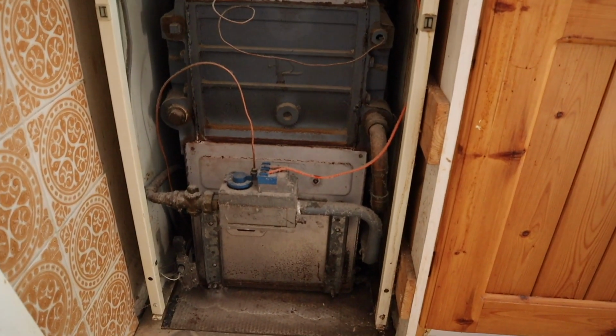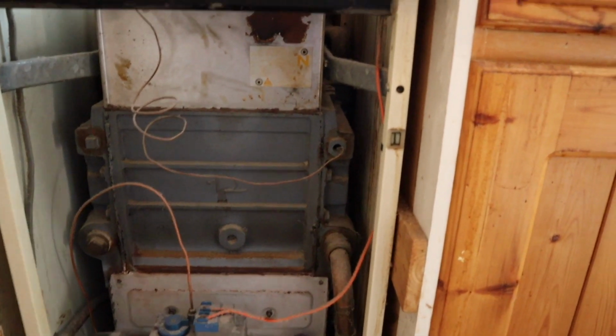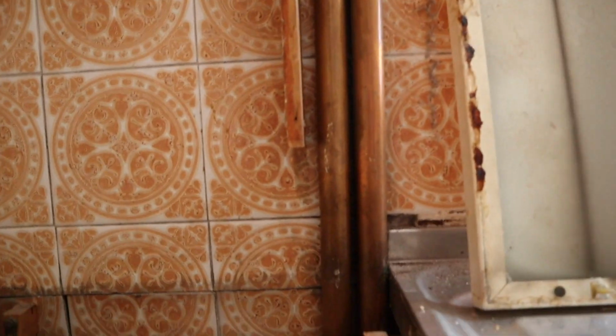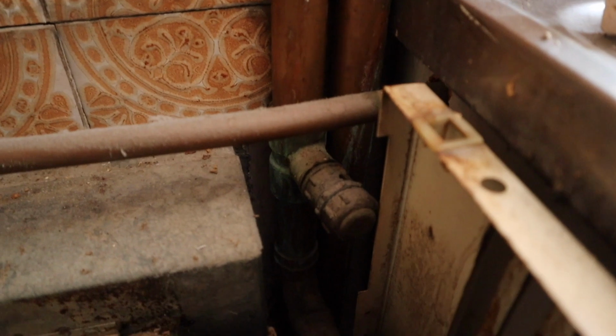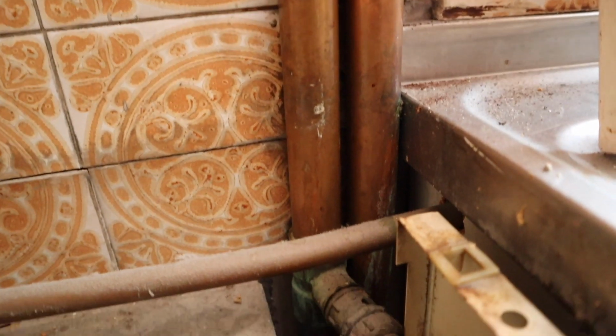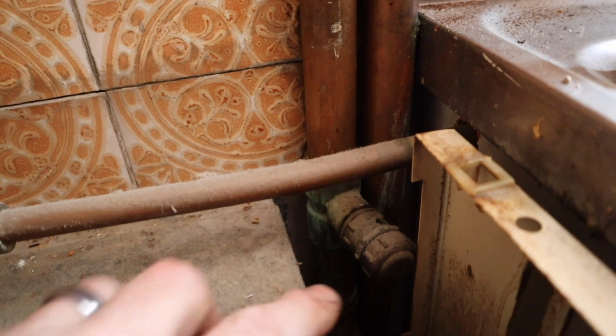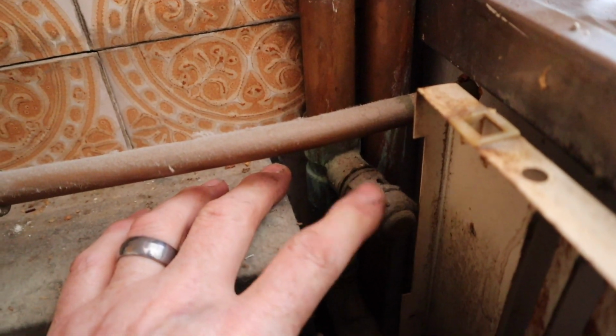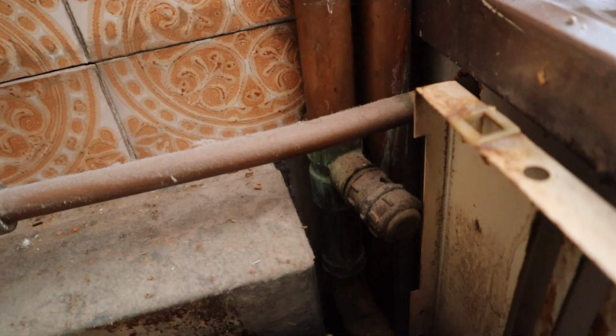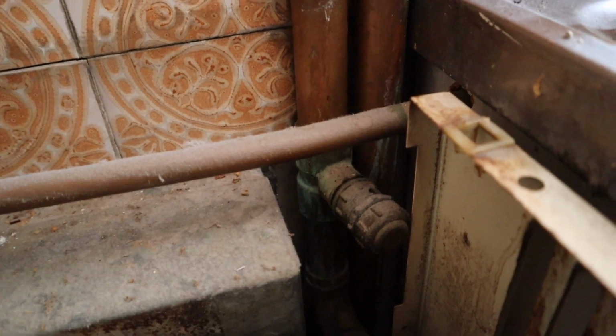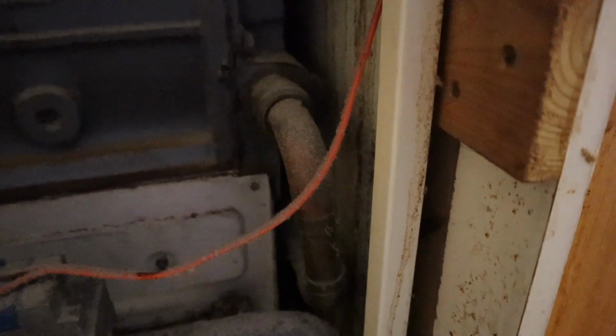Now this is the old Glowworm we're removing, balance flue. So the two 28mm pipes you can see here are the gravity circs going up to the cylinder. This is a relief valve which we used to put in gravity circs, so if it went over pressure for some reason it would blow off. So the one you can see here coming off the bottom is the central heating return, and at the back here is the flow. So we've got gravity hot water pump central heating.